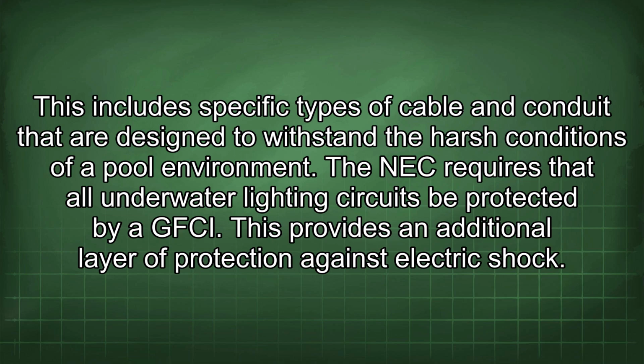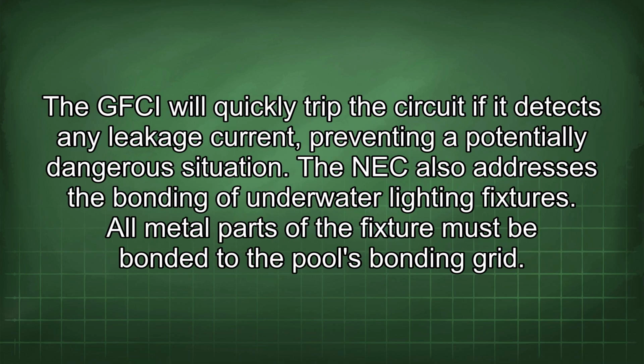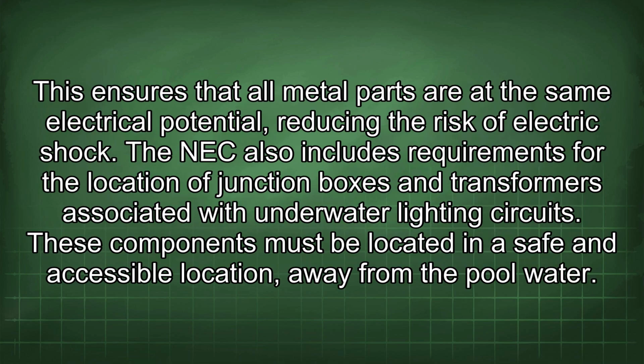The NEC requires that all underwater lighting circuits be protected by GFCI. This provides an additional layer of protection against electric shock. The GFCI will quickly trip the circuit if it detects any leakage current, preventing a potentially dangerous situation. The NEC also addresses the bonding of underwater lighting fixtures. All metal parts of the fixture must be bonded to the pool's bonding grid. This ensures that all metal parts are at the same electrical potential, reducing the risk of electric shock.